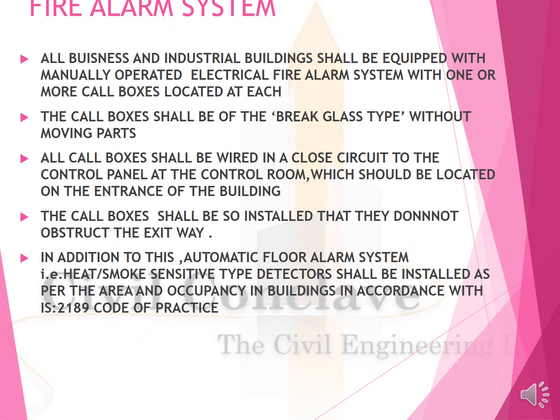Fire alarm system. All business and industrial buildings shall be equipped with a manually operated electronic fire alarm system. The call boxes shall be of the break glass type without moving parts. All call boxes shall be wired in a closed circuit to the control panel of the control room, which should be located at the entrance of the building. The call boxes shall be installed so that they do not obstruct the exit way.